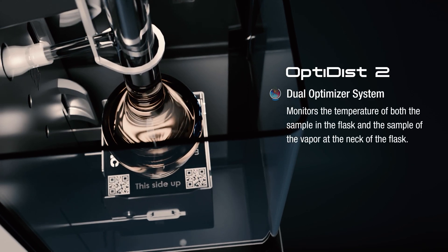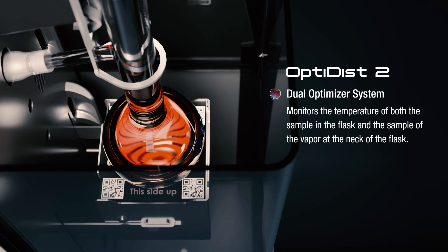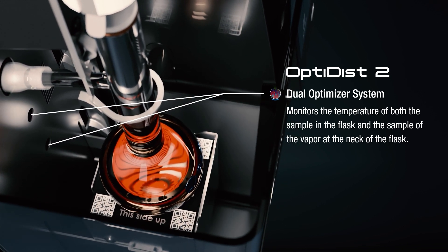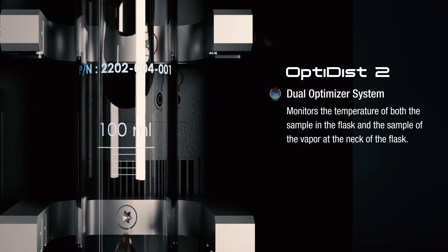The dual optimizer monitors the temperature of both the sample in the flask and the sample vapor at the neck of the flask, so that the heating rates can be controlled and optimized to ensure compliance with the distillation requirements. This is particularly important with difficult samples and ensures OptiDist 2 is most successful at running these samples on the first try.